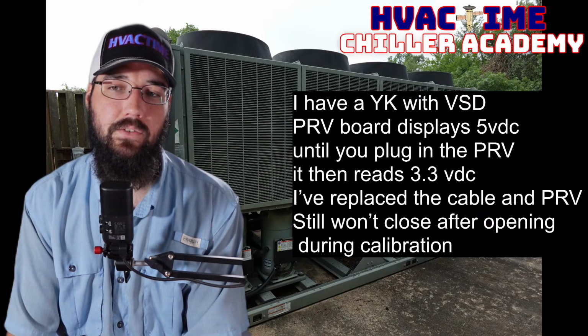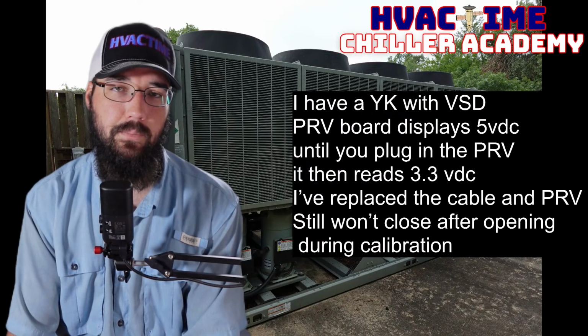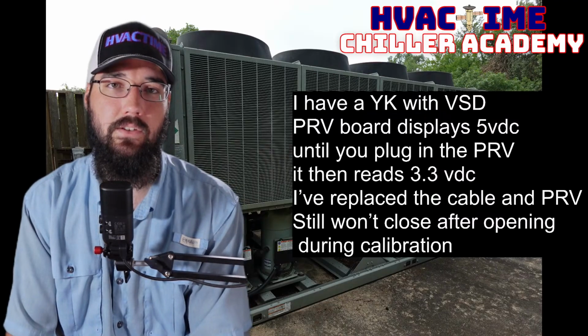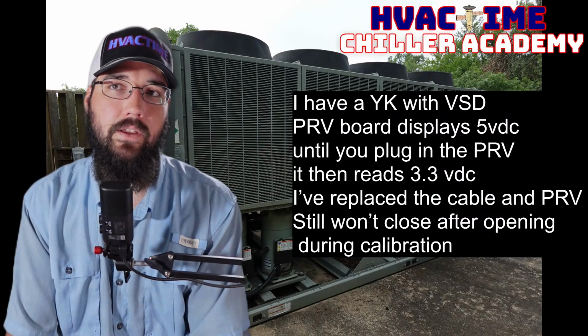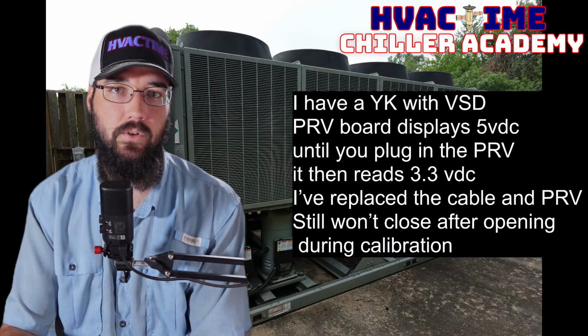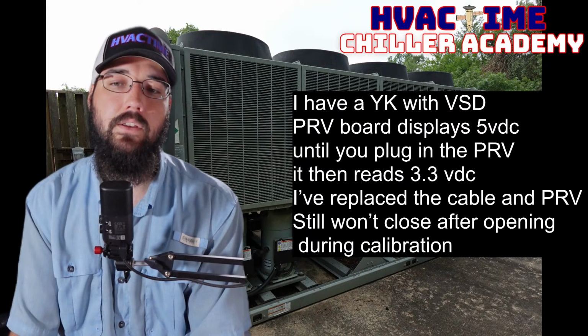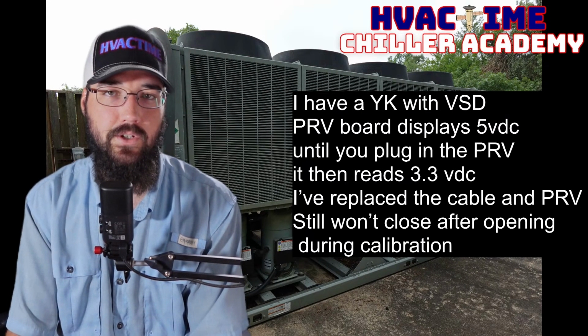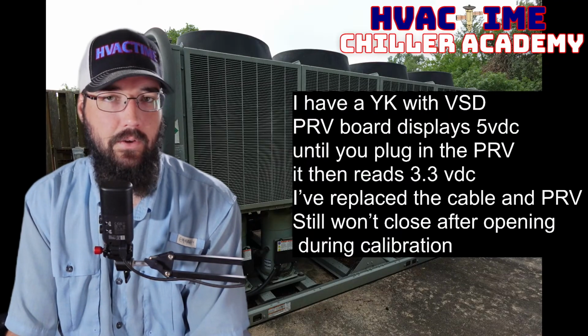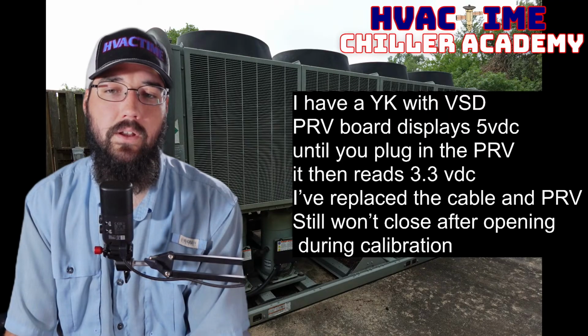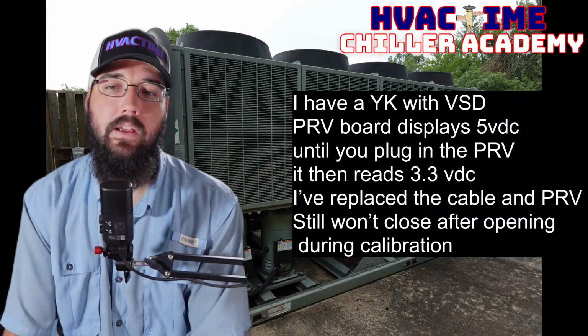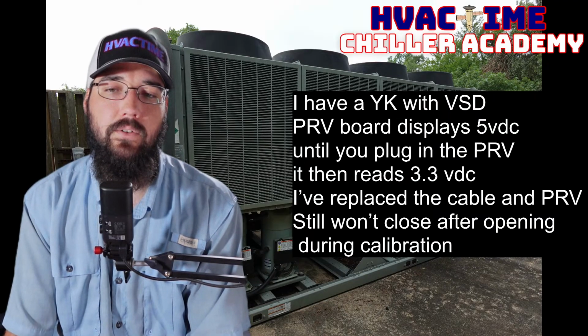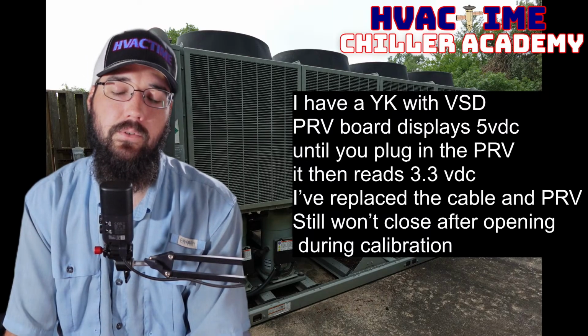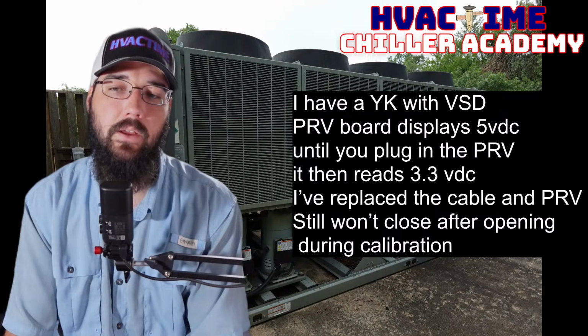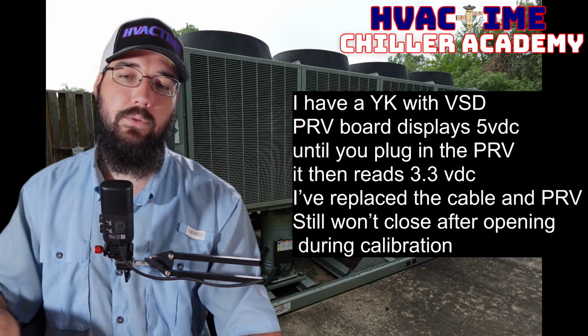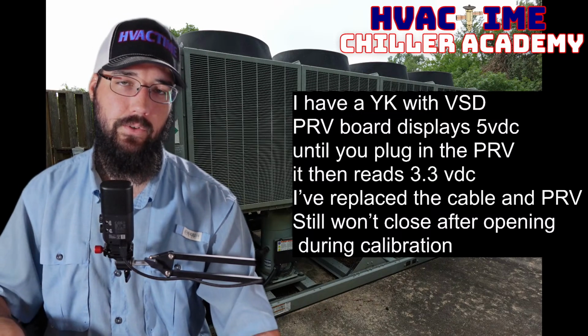So yes, if it's the PRV sensor, the module will display a 5 VDC signal until you plug the sensor in. And then as you rotate the sensor around and change its resistance value, the VDC reading at the module is also going to change. That's how it's supposed to be. Now that won't affect the actuator itself, so those are two different things. Maybe this is where things are getting mixed up for you. The actuator is a separate thing from the sensor and why it's reading that way.